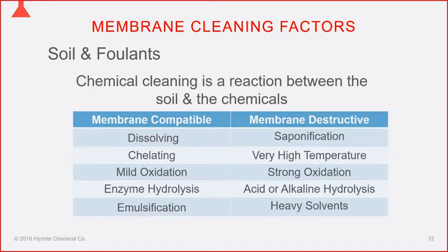When doing a chlorinated alkaline wash on an MF or UF unit, maintain chlorine on the final wash between 150 and 180 ppm and never go above 200 ppm. Above 200 ppm you can start oxidizing the membrane surface, opening up pores and causing passage of molecules you don't want. Likewise, very hot acid or very hot caustic at high concentrations — used for acid or alkaline hydrolysis on evaporators — require pH far outside the acceptable range for membranes.